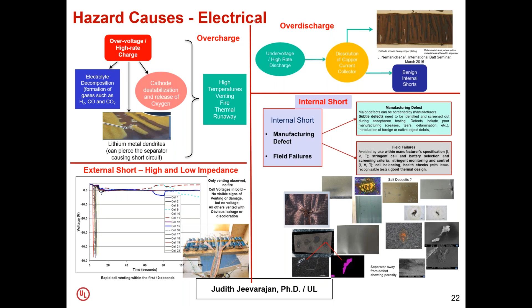But what we found is that when we put cells in series or parallel connections, it no longer works as expected. In this particular case, with 14 cells in series, we found that the cells went into catastrophic thermal runaway, with temperatures above 500 degrees C. When we did the same test under a vacuum condition, we found benign CID activation of every single cell. So the heat dissipation that occurs in an ambient condition versus a vacuum condition really changes whether that CID results in a catastrophic failure or not.